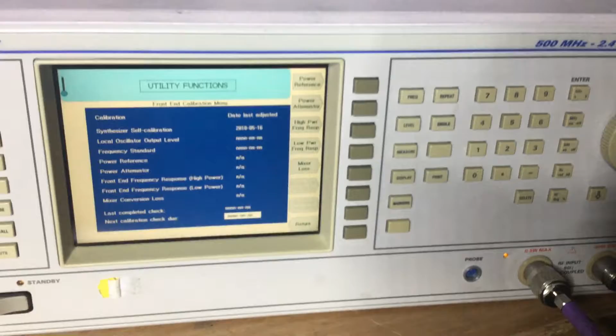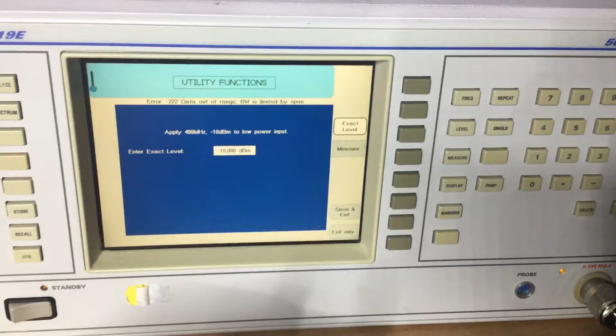And I was trying to follow the instructions, because basically it says, for example, if you go into this function, it says apply a frequency at a level to low power input, and then press enter to continue, you see. So enter exact level, so that's what you put in. Then you go through this timed sequence of it measuring it, and then it'll store the DAC in memory, and then you move on, advance to the next test. So that's a little rundown on that.